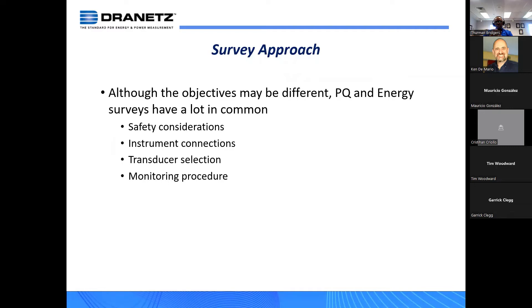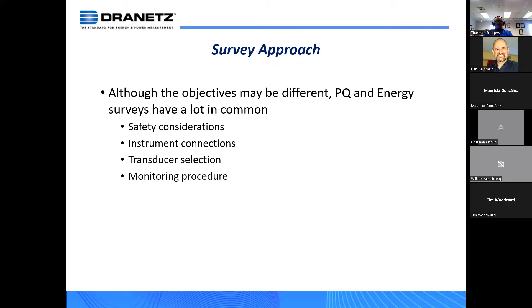The approach may differ based on the objective, but surveys have things in common: safety considerations, instrument connections, and transducer selection. An example of transducer selection is which current probes you're using. I often see scenarios where someone uses a current probe not quite appropriate for the application — maybe the range is too large, or the current being monitored is too small, which can have adverse effects on your data set. There's also the monitoring procedure itself, and the approach that we've seen over nearly 60 years as far as what's most efficient and yields the most results.